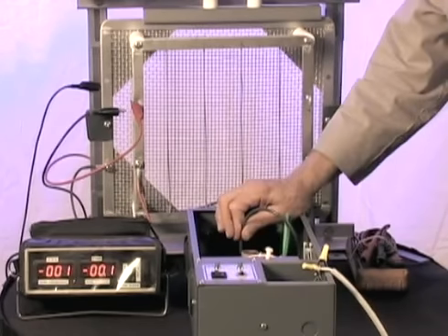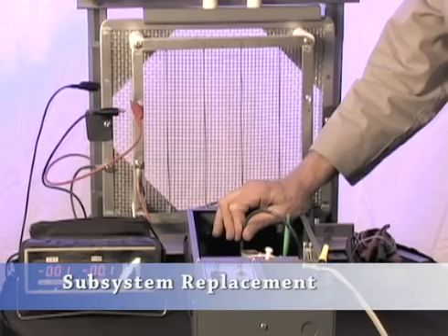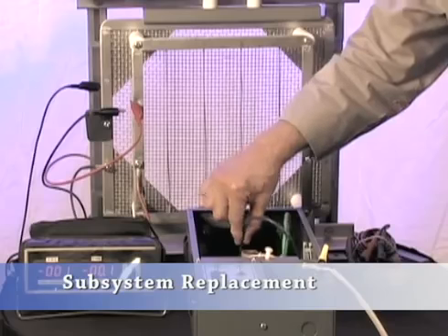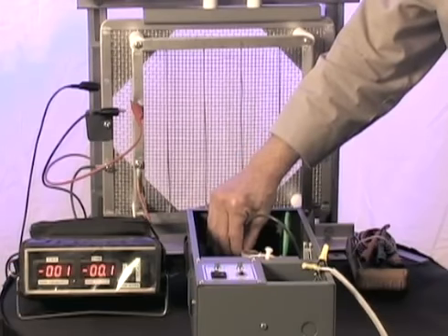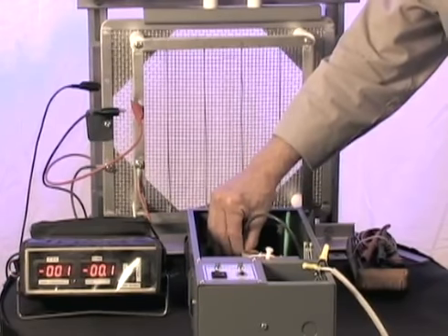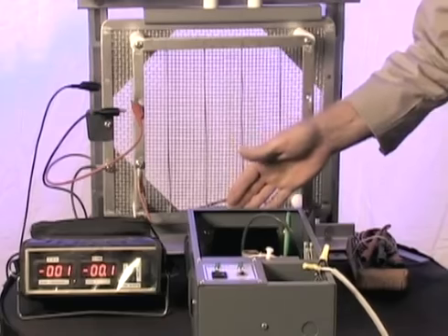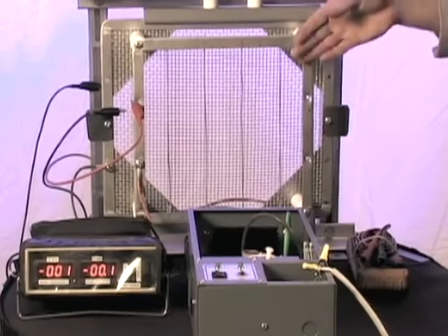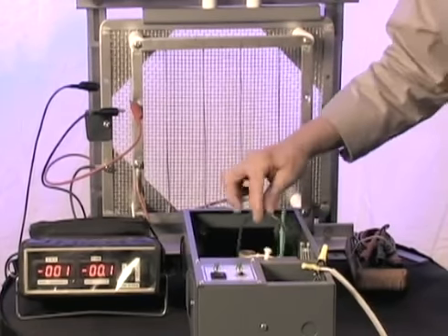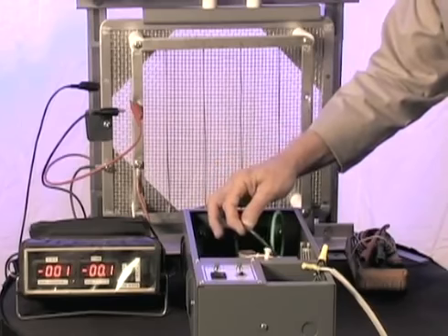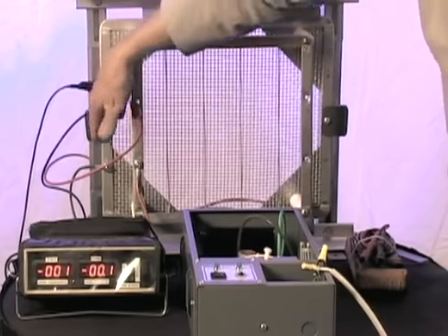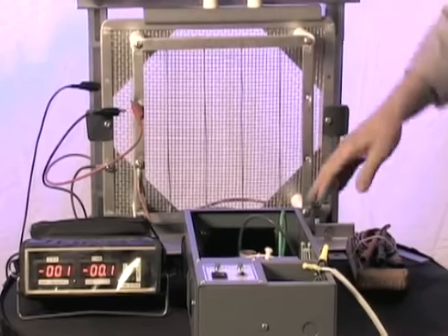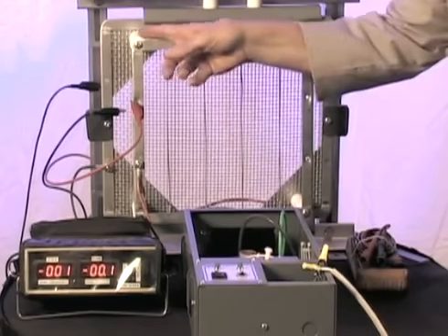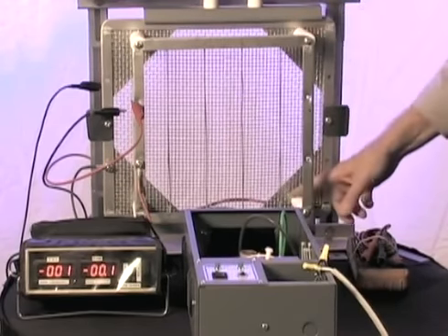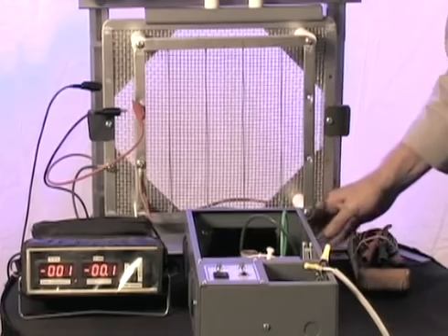If you pulled the wire off the board and the high frequency light comes on and the fuse is still good, and when you put the wire back on the tab, it goes out, there's probably a problem between the generator and the electrode set. This would involve troubleshooting problems with the cable, connections at the screen set, or conditions of contamination on the plastic surfaces which hold the screen set isolated from its surroundings.